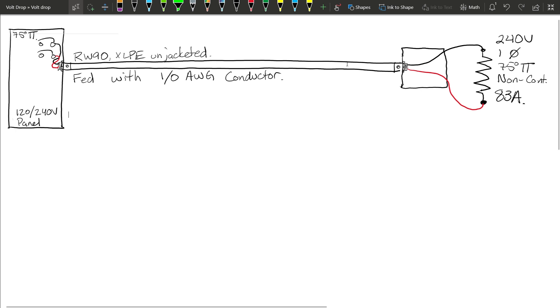Hey, what's up everyone — thanks for joining me. In this video we are performing a volt drop calculation specifically using Table D3 from the 2018 Canadian Electrical Code. We have a 120/240 volt panel supplying an 83 amp load. Specifics: it's a 240 volt single phase load with 75 degree terminations, it's a non-continuous load, fed with a 1-aught gauge RW90XLPE unjacketed conductor.